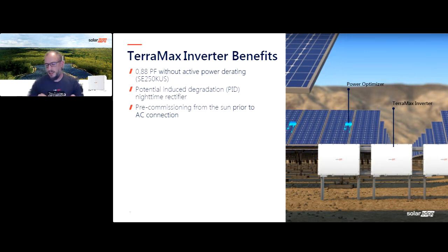So you can set your grid code, you can search for the optimizers that are out in the array, and you can set up all the stuff that, with a typical string inverter, you would have to wait until you get AC grid power to do, or you have to have both DC and AC. We have the ability to power from either the DC side or the AC side, so it gives you a lot of flexibility, and this saves time. A lot of times, projects that we are working on are waiting on interconnection, and they can't do anything until they get that grid connection. And then once they get permission to operate, it's a scramble to get ready and get the inverters commissioned. If you can get that done beforehand, it saves a lot of time up front.